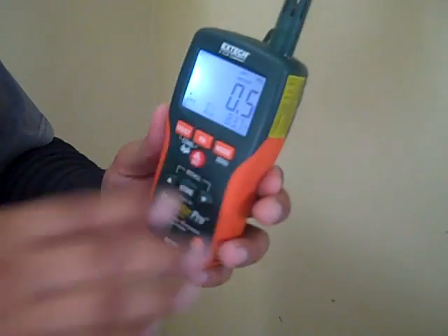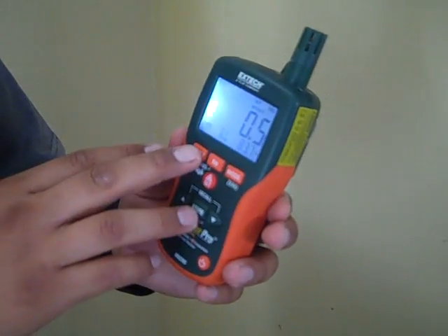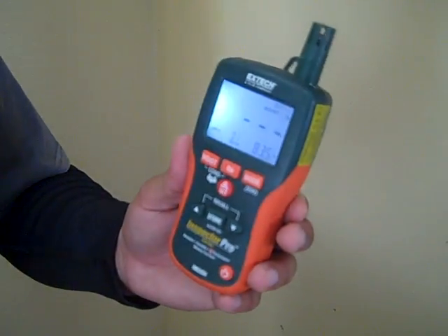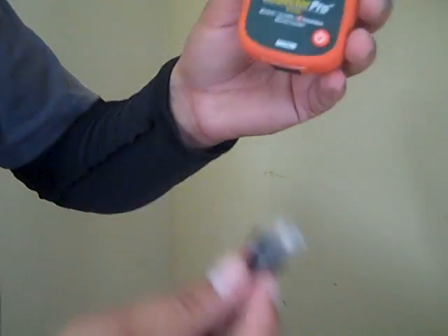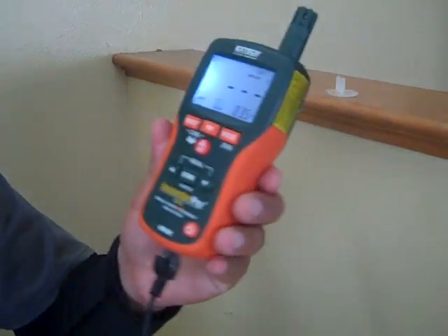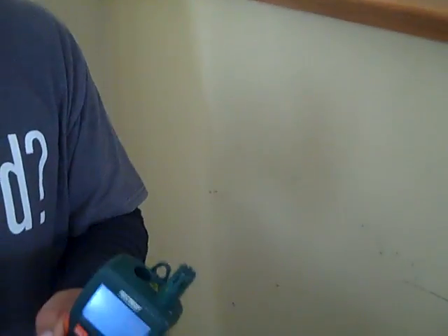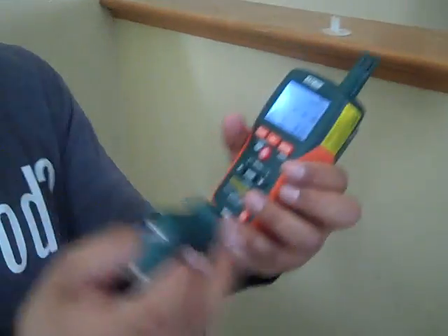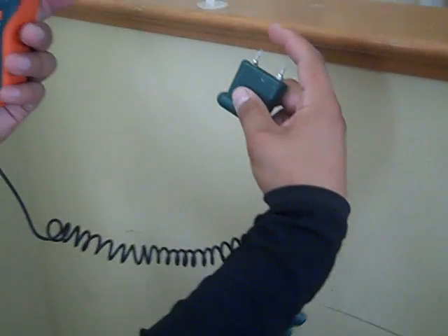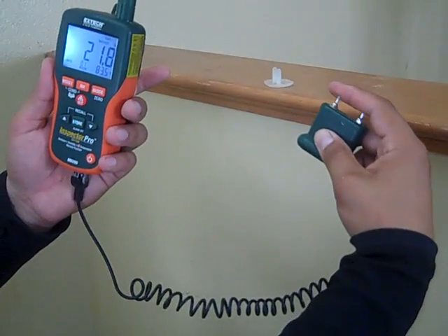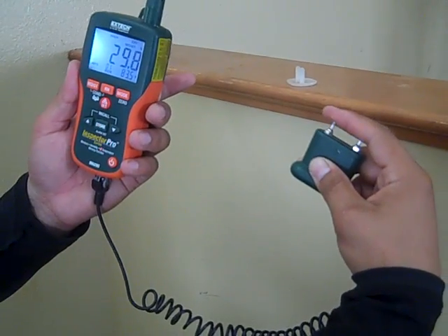For the external mode, press the mode button once again, moist button once again, hook up the external probe to the external plug-in, and these have probes that physically go into the wall. We'll pop this open. For example, I put my finger, which is moist, on the tips of it, and it gives us a reading.